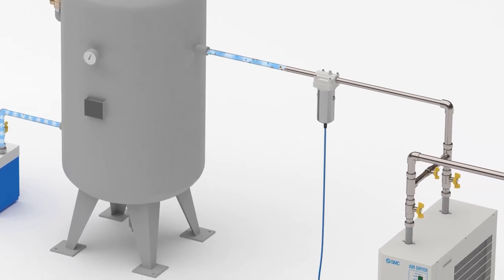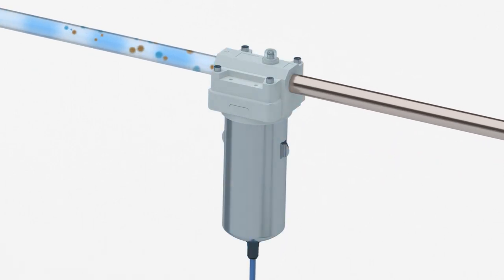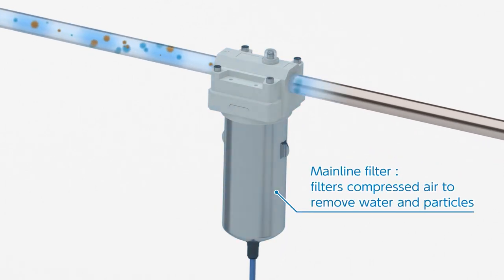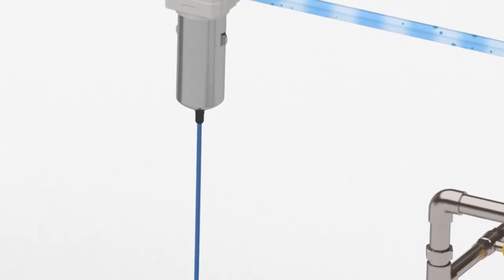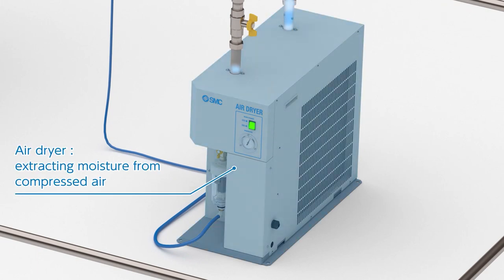Compressed air in this tank contains impurities like solid particles and water droplets. To remove coarse impurities, in the first filtering stage, the air is passed through a mainline filter. The remaining moisture in the air is extracted by passing it through an air dryer.